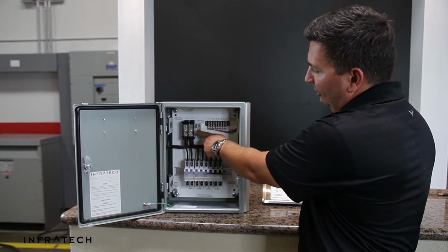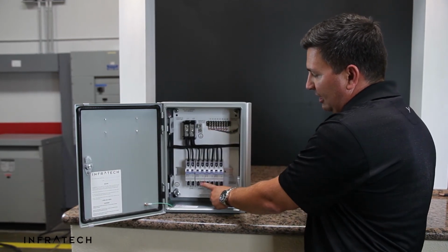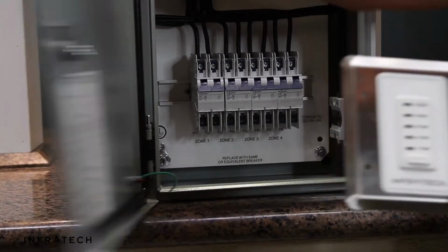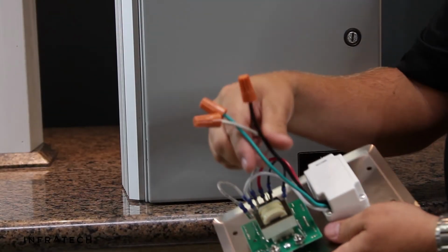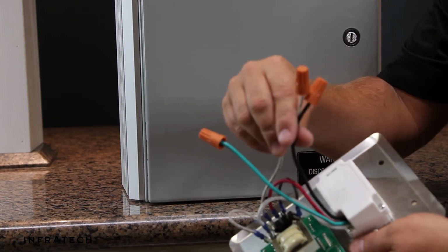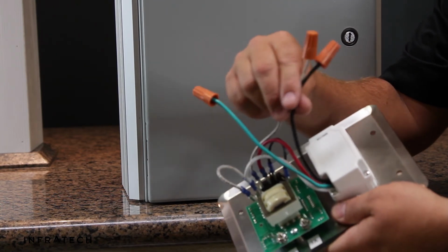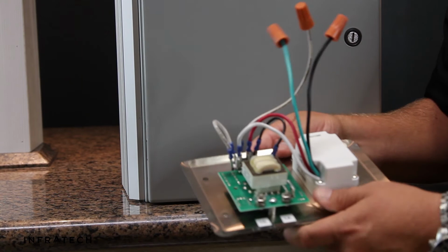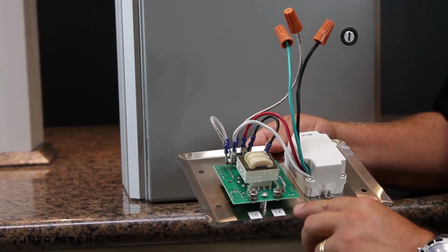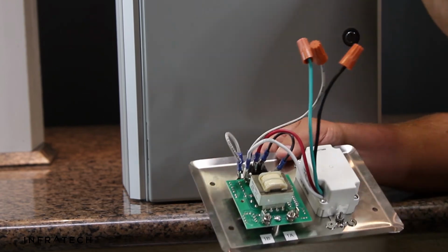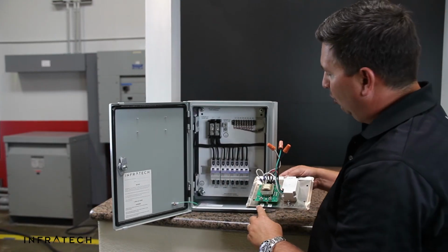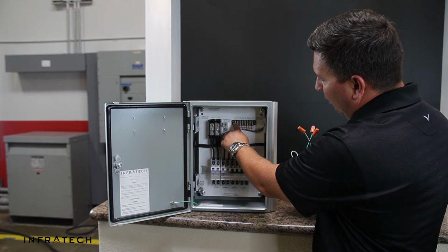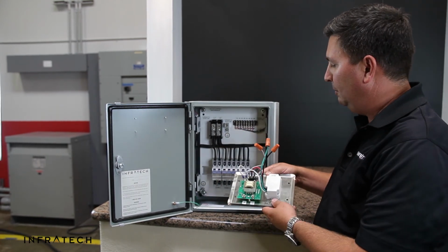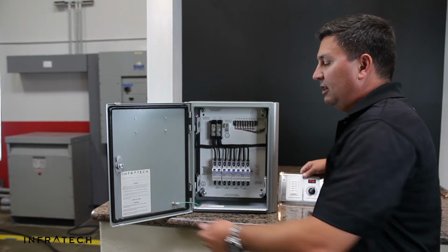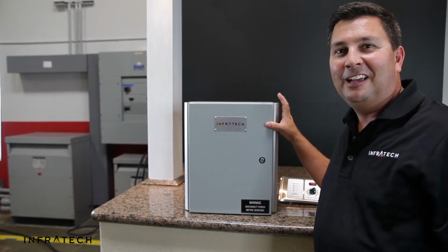Once the main power feed is connected and the high voltage lines to the heaters are connected, we can connect the analog control. The analog control will need 1 amp of 110 power. That is normally taken from a local lighting or power circuit. So you'll connect the 1 amp of 110 to the black and the white, and then the green for the ground. You'll then connect the 10 volt DC control signal to 1A, 1B, 2A, 2B, etc., depending on your control configuration. 1A and 1B will connect to the contact strip labeled 1A and 1B for the low voltage control input. Once all the low voltage signals are connected, your control installation is complete and the heaters are ready to operate.